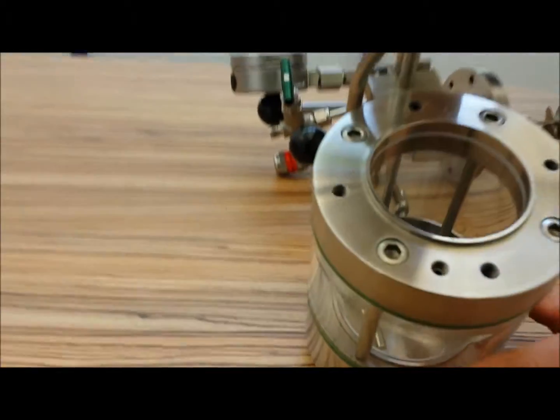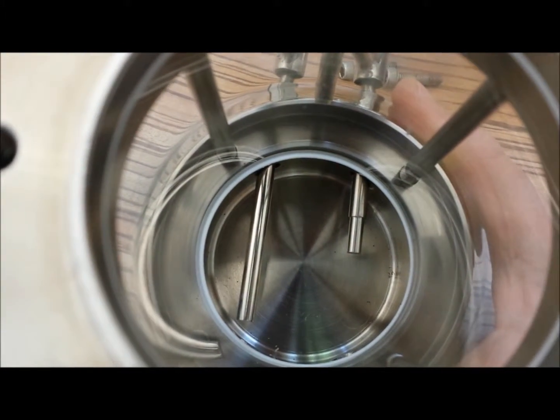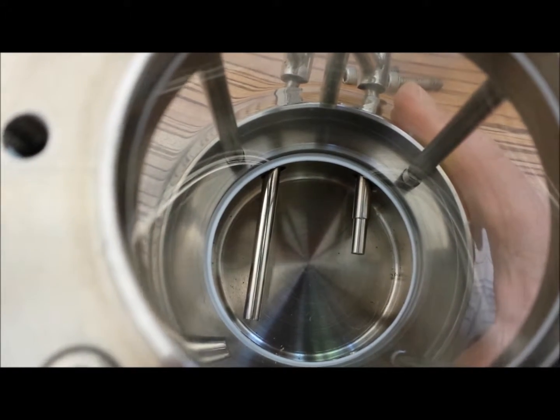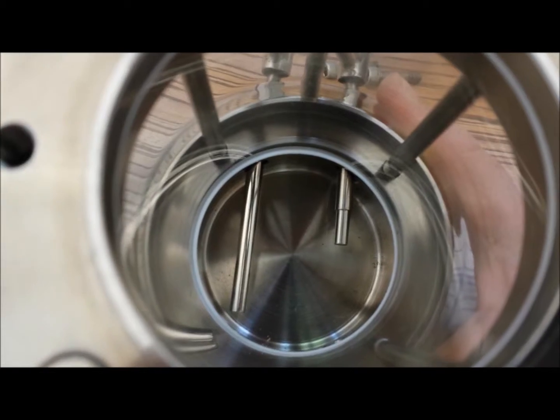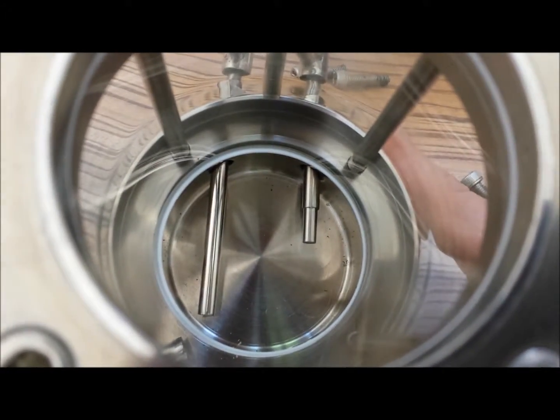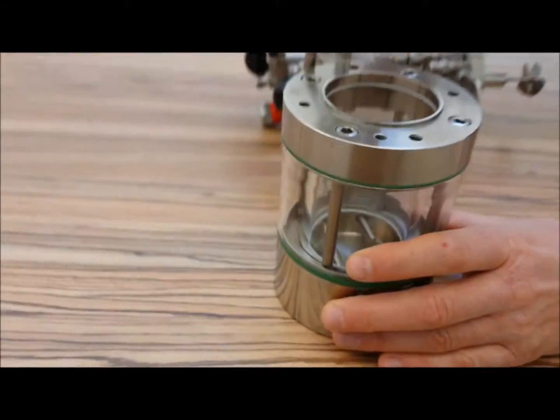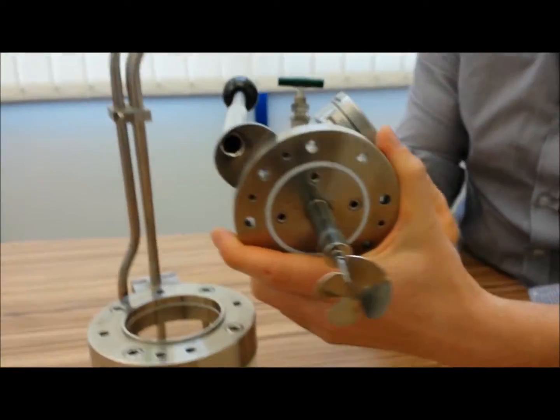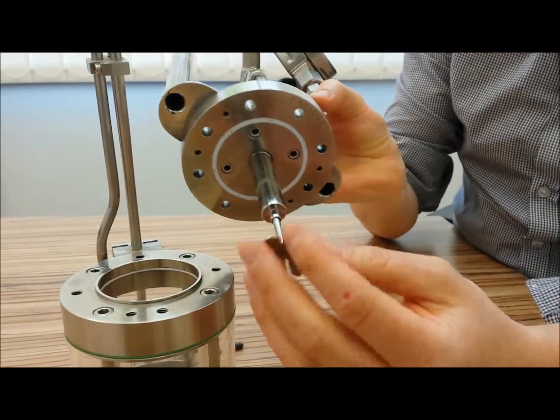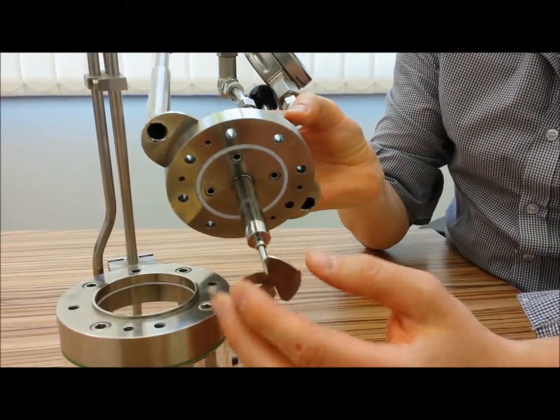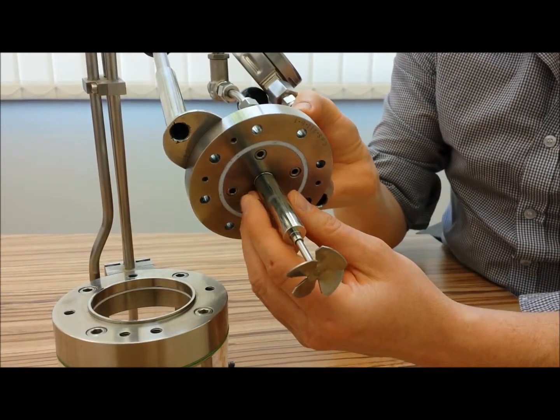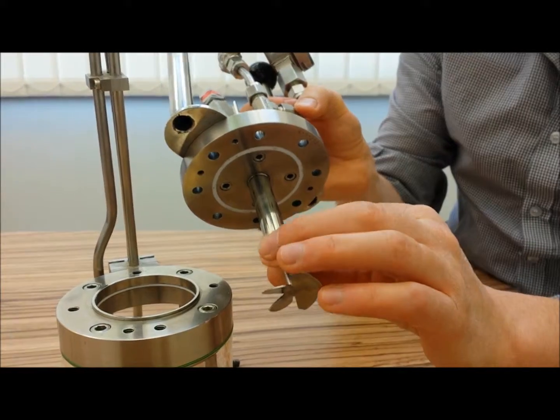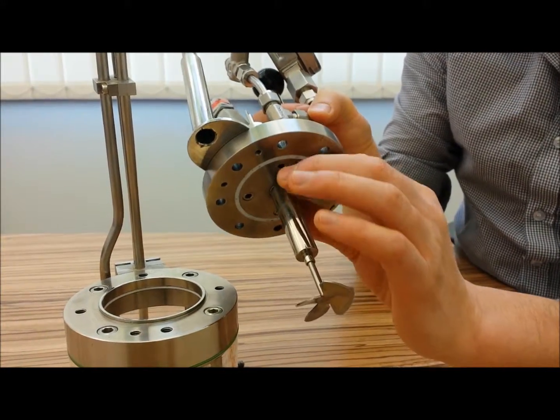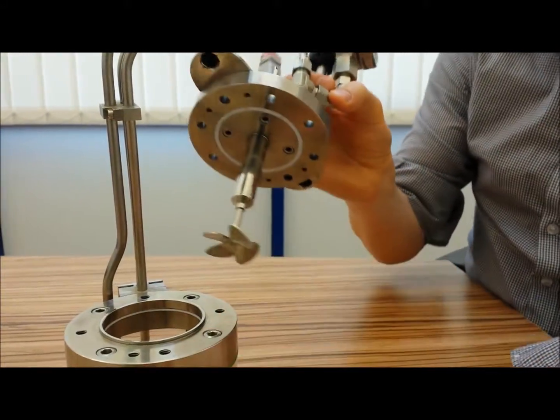When we look inside the reactor, the longer shaft rod is the validation heater, which you really don't need. It's maybe used once a year by some customers who want to validate that the factory calibration, which only needs to happen once, is done. And then the shorter one is the reactor temperature probe itself. Then if we take a look at the lid, what we have on this particular one is a propeller. We have a whole range of anchor stirrers, impellers and propellers. We also have direct drive stirrers, magnetically coupled stirrers, and torque transducers, so you can truly know the power coming from the stirrer. So I'll put that back on.